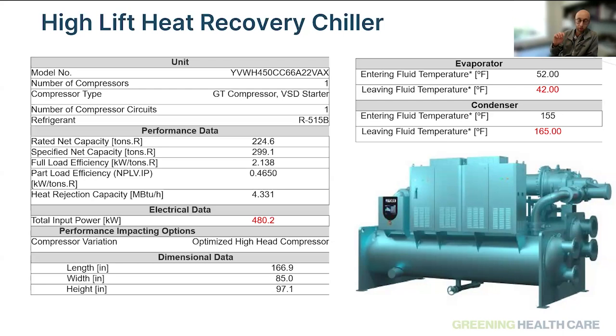You want to optimize your heat recovery machine the way this team did, with the simultaneous load hitting that peak point where there is maximum heating and cooling that can be exchanged between the two systems. So yes, if you're sizing your main cooling system to use the same machines as your heat recovery, you're going to be taking a bit of a loss. But if you have your loads studied and you have a good understanding and you have proper engineering up front, you can right size that system to run at peak performance and get simultaneous heating and cooling COPs of 4 or 5 plus, even higher.